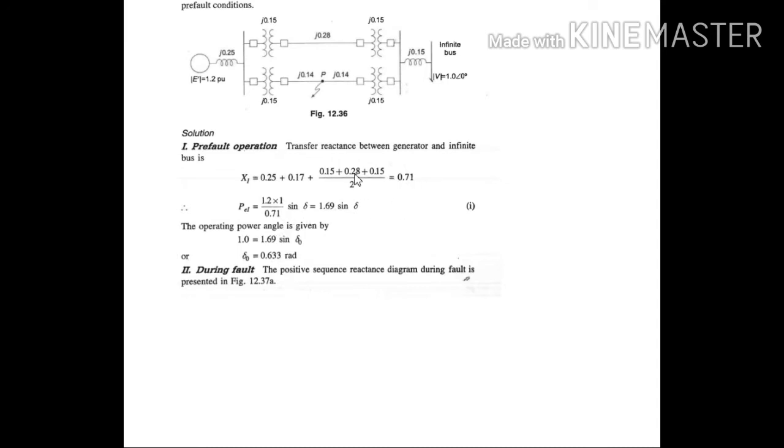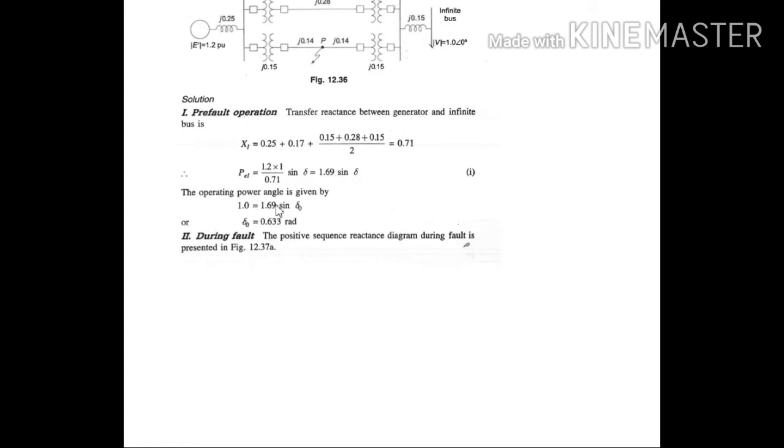Then substituting all the values in the expression PE equals EV by X sine delta. The value is 1.69 sine delta. The operating power angle is given as 1 equals 1.69 sine delta 0. This expression is PM initial loading. PM0 equals PE0 equals PE1 or Pmax1 sine delta 0. From this we obtain delta 0 as 0.633 radian.